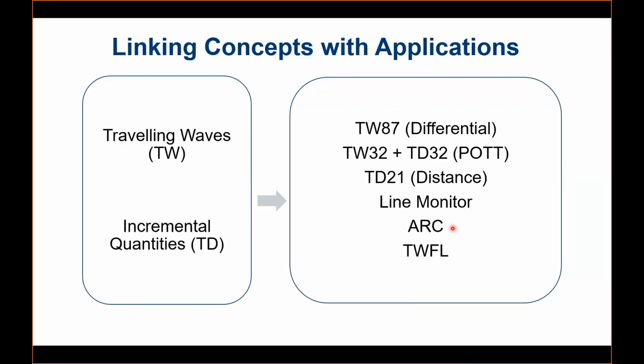Auto reclosing is one of the applications we can achieve from these technologies. It is especially useful for lines with challenges like tapped loads or hybrid configurations, where some part is overhead line and some part is underground cable, or a combination. One of the most challenging things is fault location. Fault location for transmission lines has been a challenge in the past. It is partly solved by distance relays with impedance-based methods, which give you an idea where the fault is, but it's still not that accurate. You have to patrol maybe 5% or 10% of the line to find the actual fault.